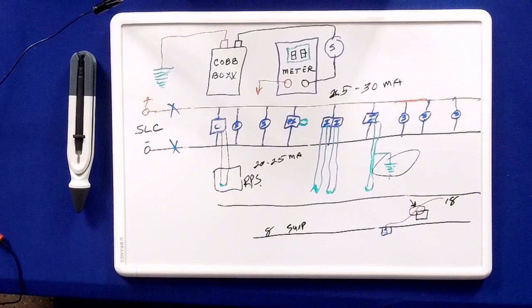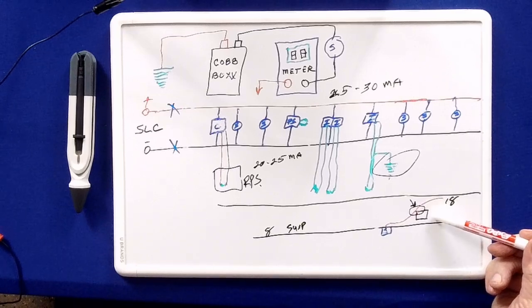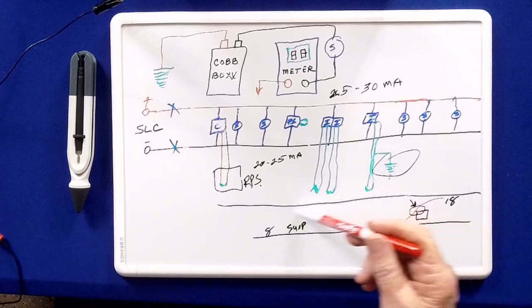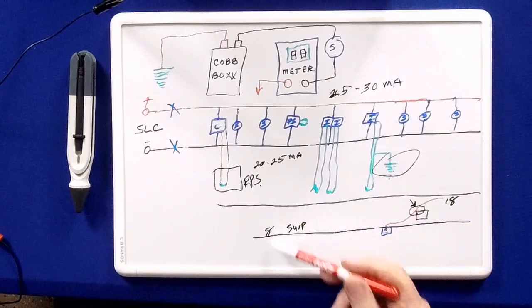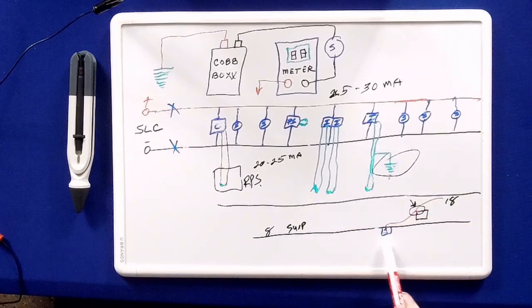So it stopped. I went, okay, turn it back on, start hearing the crackle again. Not quite as bad, but still heard the crackle. I said, okay, where's that HVAC unit at? He says, well, that's the HVAC unit down there at the concession stand on the 3rd level. So we go down there, and as you can see by this drawing here, had about an 18-foot ceiling with an 8-foot suspended ceiling, and they had a smoke detector sitting on that suspended ceiling.